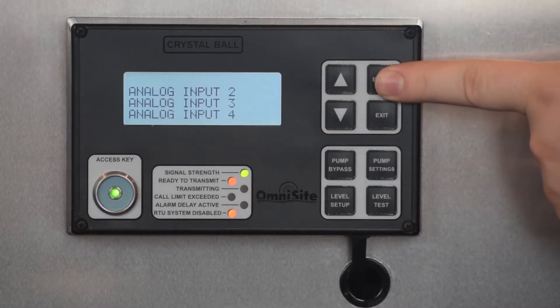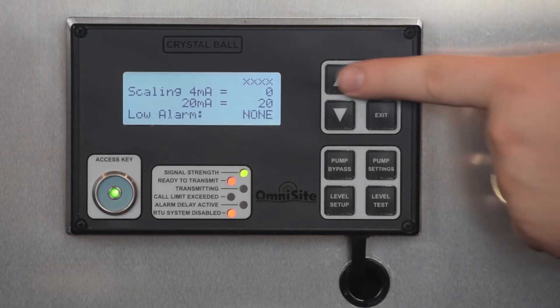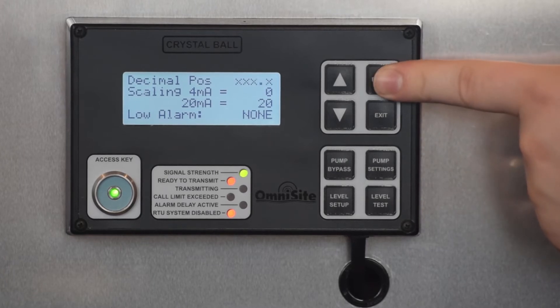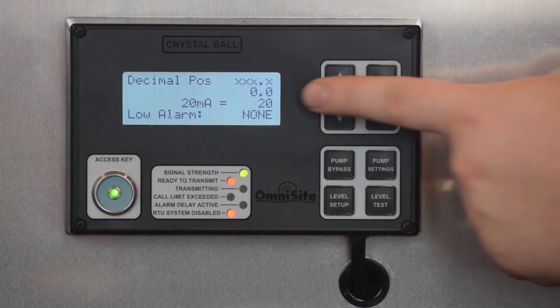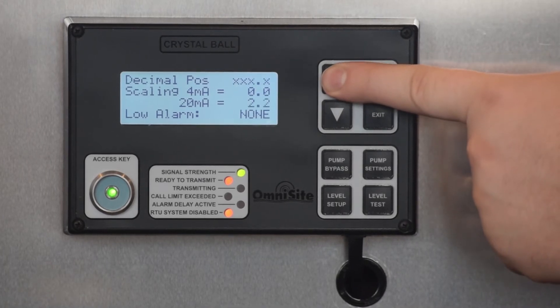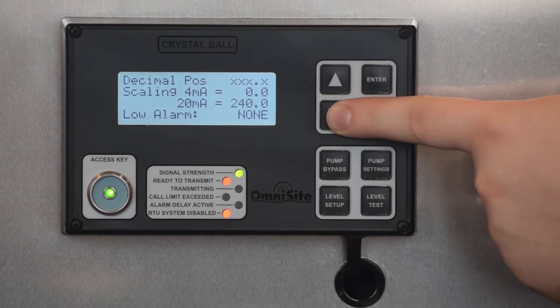Next, select Setup Analog Inputs and press Enter. Here you will be configuring analog input 1, which you previously wired up with your level transducer. The first setting is decimal position, which allows you to adjust the accuracy of your level output display. Make sure to select a setting that works for your installation. For this tutorial, I've set it to display 1 tenths. Next, enter the scaling for your level transducer. The OmniSite level transducer used in this tutorial is scaled for 0 to 20 feet, or 0 to 240 inches. The scaling you enter here should match the scaling indicated on your transducer device. My settings are 0 to 240.